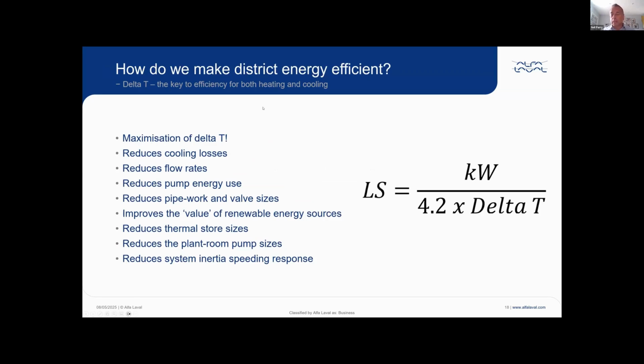So I mentioned I'd talk a little bit about efficiency. There is only one rule of thumb that we look at, whether it's heating or cooling, and that is the maximization of the delta T. That's the difference between the flow temperature out and the return temperature coming back. The greater that difference, the greater the efficiency of the network. This little equation here, very basic, says that the flow rate you need is based on the power required divided by your thermal transfer coefficient times delta T. So the bigger the delta T is here, the smaller the flow rate is that's required to provide that amount of energy.